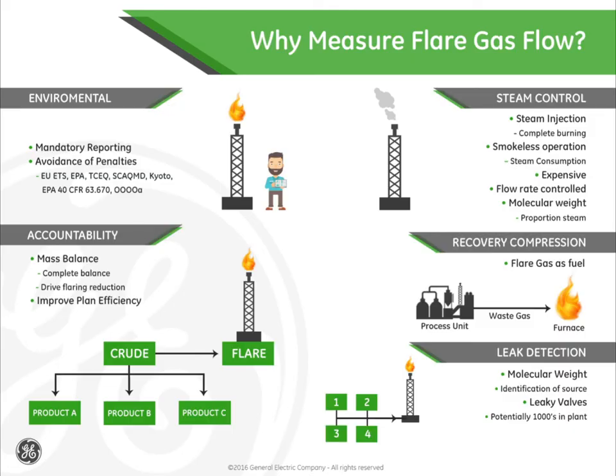Why measure flare at all? Okay, we know how a flare meter works and what makes up a flare meter, but why measure flare gas at all? As I mentioned earlier, flares exhaust waste gas to the atmosphere, and for this reason, most governments require some form of measurement and reporting. Aside from regulations, however, a flare meter can aid in plant balance and yield control within a refinery or process plant.